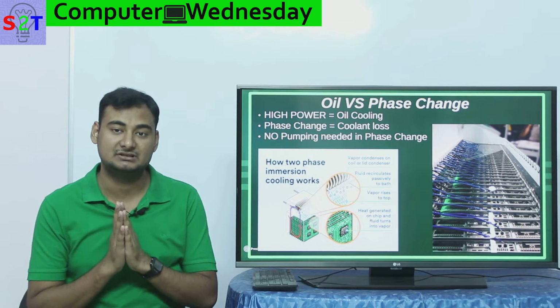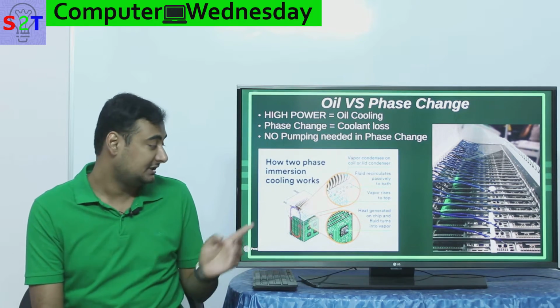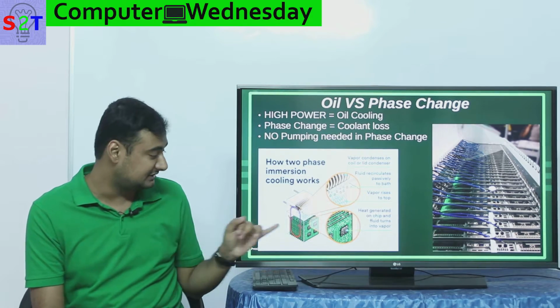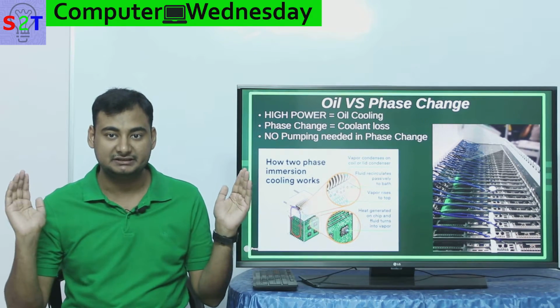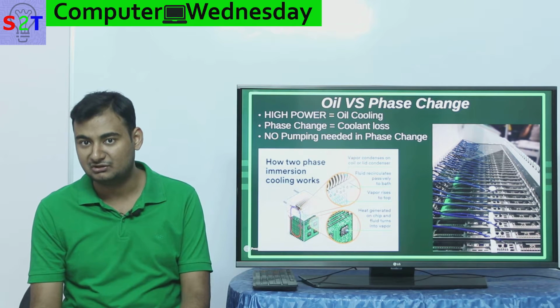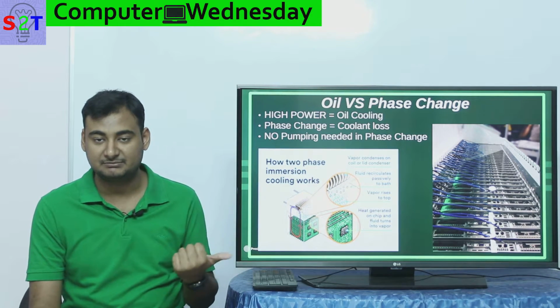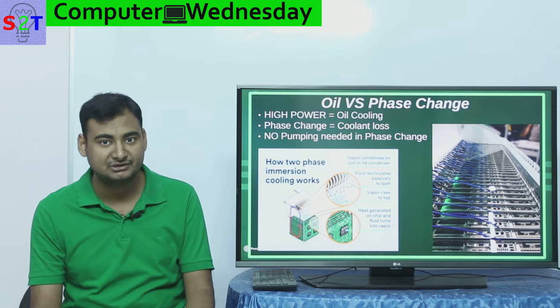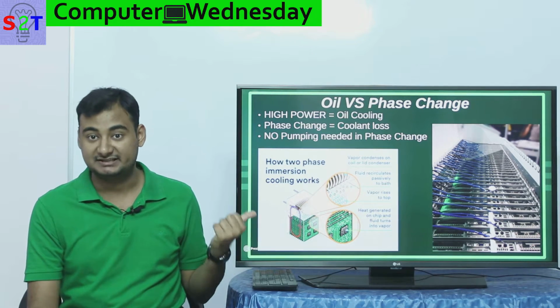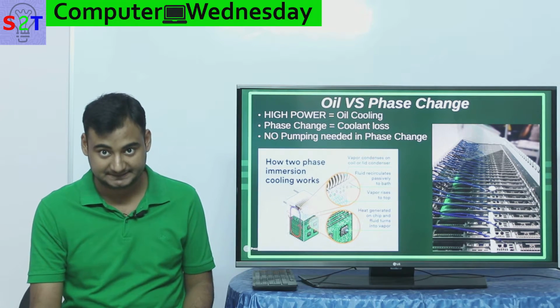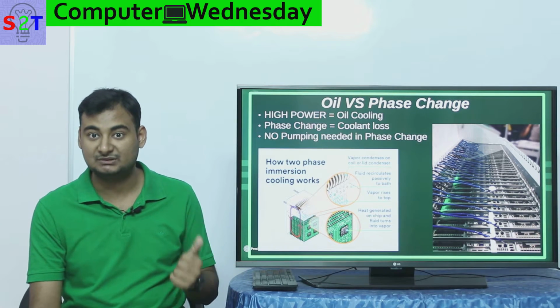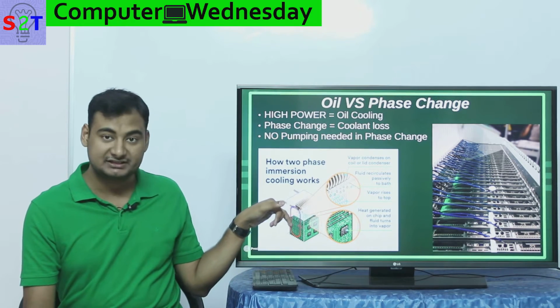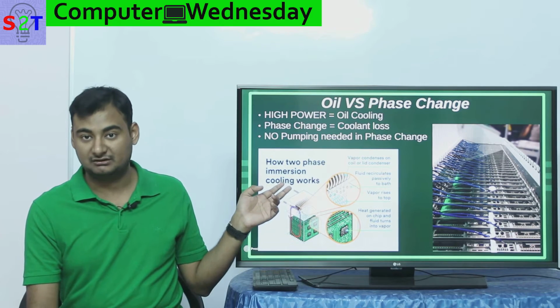But if you have something that is consuming a lot of power, this is not a good solution. Imagine this can give you, per rack, upwards of 100 kilowatts. If you dump something generating heat upwards of 200 kilowatts, this will not be able to handle it, simply because it will evaporate way too quickly. And not to mention, if for some reason your cooling tower or this cooling system fails, it will boil off way too quickly.